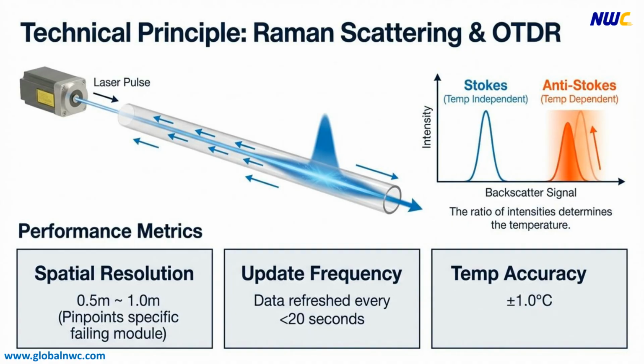This system combines the Raman scattering phenomenon with OTDR technology to precisely calculate temperature by analyzing the intensity ratio between Stokes and anti-Stokes signals within the optical fiber. With an excellent spatial resolution of 0.5 to 1.0 meters, it can accurately pinpoint the location of thermal anomalies. A fast update cycle of under 20 seconds enables continuous real-time monitoring. As a result, the system maintains a high temperature accuracy of plus or minus 1.0 degrees Celsius, reliably capturing the thermal behavior of critical equipment.